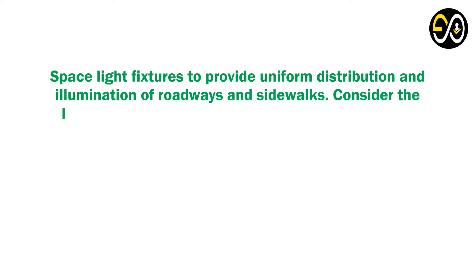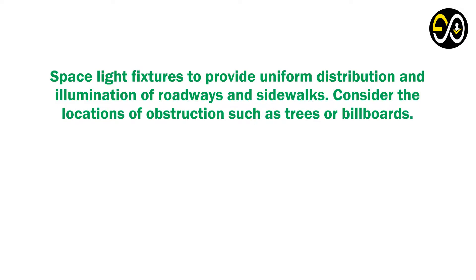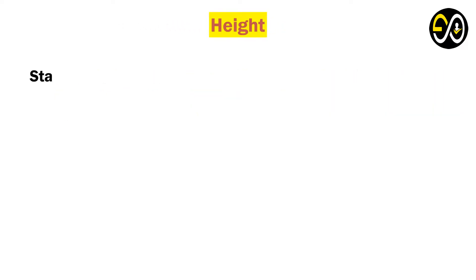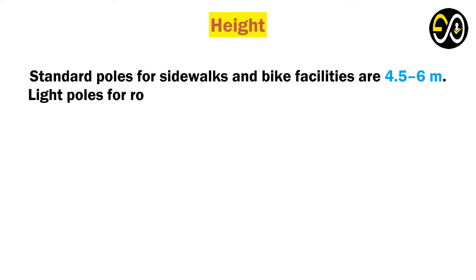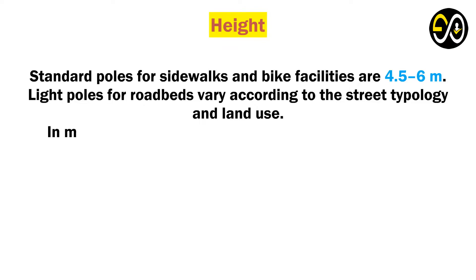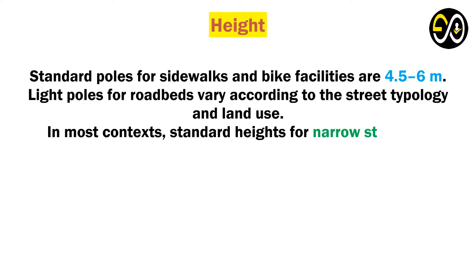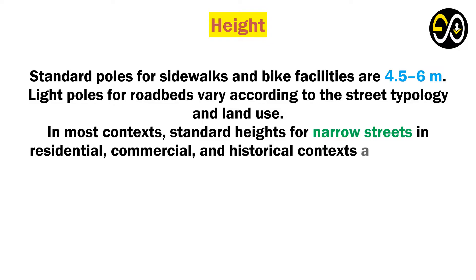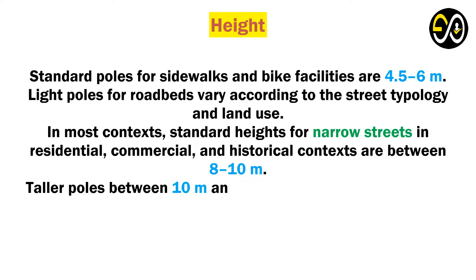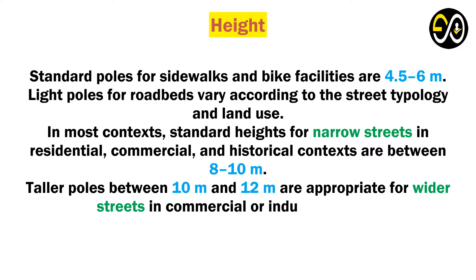Space fixtures to provide uniform distribution and illumination of roadways and sidewalks. Consider the locations of obstructions such as trees or billboards. Standard poles for sidewalks and bike facilities are 4.5 to 6 meters. Light poles for roadbeds vary according to the street typology and land use. In most contexts, standard heights for narrow streets in residential, commercial, and historical contexts are between 8 to 10 meters. Taller poles between 10 meters and 12 meters are appropriate for wider streets in commercial or industrial areas.